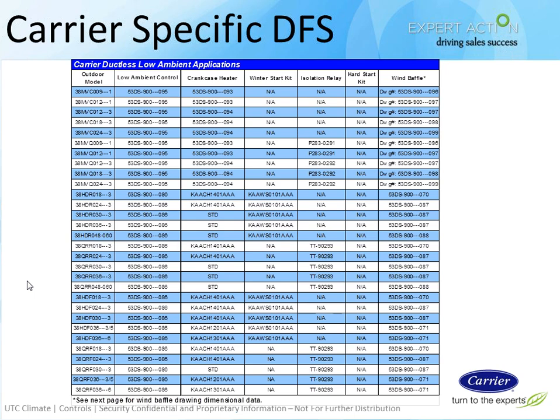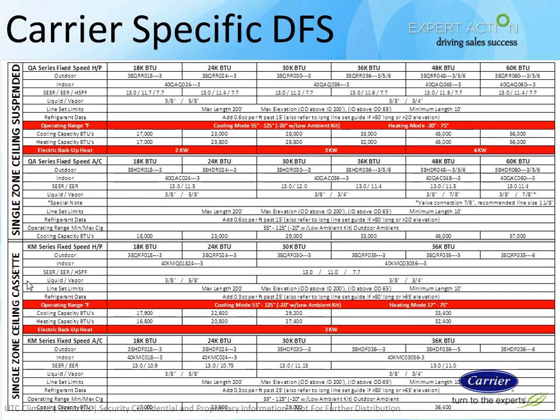I mentioned the minus 20 low ambient operation equipment. This is a list of the accessories that are needed to achieve minus 20 degree low ambient operation. We have the low ambient control, the crankcase heater, winter start kits, isolation relays, and wind baffles. This chart can be downloaded for your use from HVAC partners. This is a sample list with performance data, electrical data, and so on from HVAC partners as well.